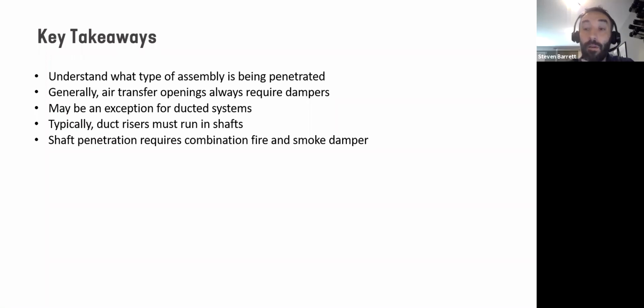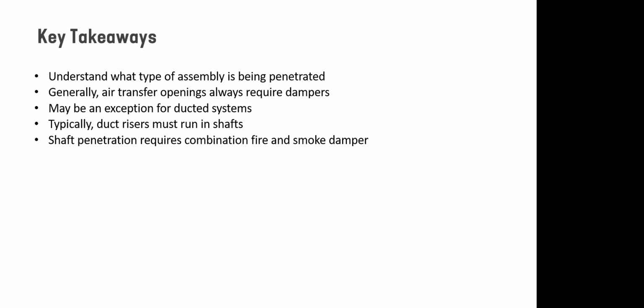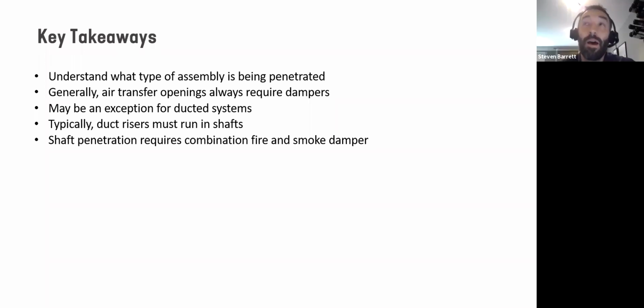Now, the commentary says that's typically good advice to utilize. My understanding was a little bit different, that the issue wasn't that it's fully ducted, it's that it requires a minimum gauge 22 ductwork, in which case I don't think flex ducts meet that requirement. So that may be from the fire partition section where it says fully ducted, not the fire barrier section where it's not just fully ducted, but it's also minimum 22 gauge.